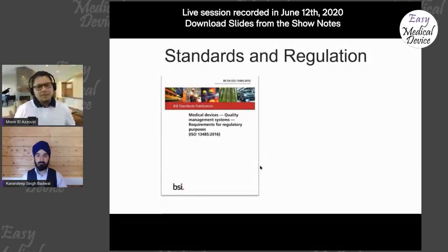People that are in the medical device field know CAPA because it's specifically requirements for ISO 13485. It's chapter 8, which one we said? 8.5.2, I think, and 8.5.2 and 8.5.3, I believe. Yeah, 8.5.2 and 8.5.3. 8.5.2 is for corrective action, and 8.5.3 is for preventive action. So you can find that there.